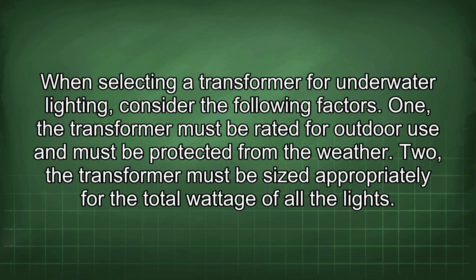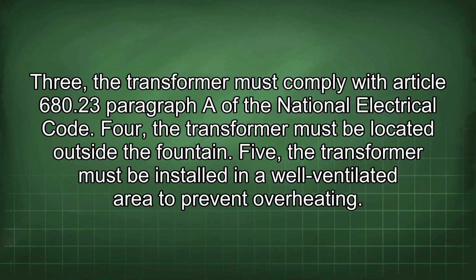When selecting a transformer for underwater lighting, consider the following factors. 1. A transformer must be rated for outdoor use and must be protected from the weather. 2. The transformer must be sized appropriately for the total wattage of all the lights. 3. The transformer must comply with Article 680.23 paragraph A of the National Electrical Code. 4. The transformer must be located outside the fountain. 5. The transformer must be installed in a well-ventilated area to prevent overheating.